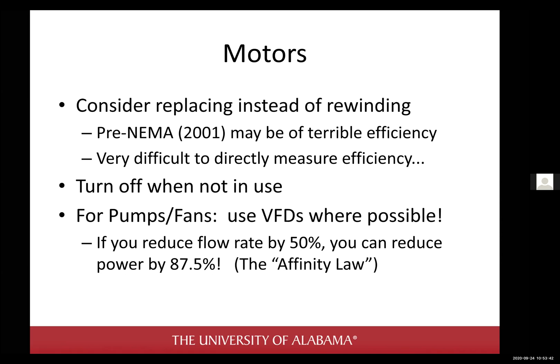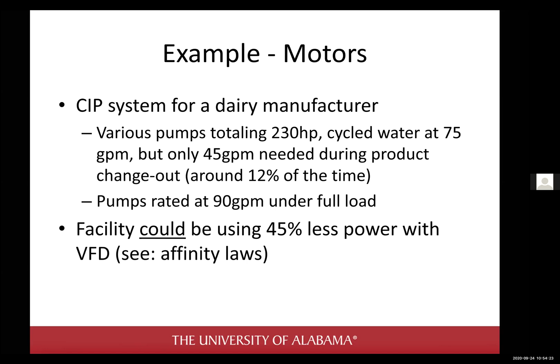In fact, a quick example: a recent dairy manufacturer using 230 horsepower on a clean in place system. They were running 75 gallons per minute, but they only needed 45 gallons per minute. Based on the affinity law I was talking about, by using a VFD and going from 75 to 45 gallons per minute, they could be using 45% less power. And they already had VFDs in place. We just told them to put in either a control system or just pay someone to go around and check this every couple of hours.